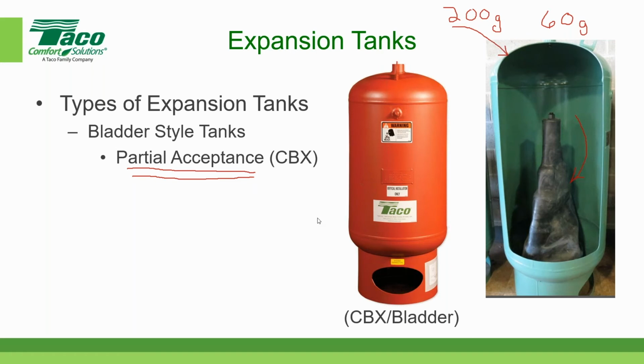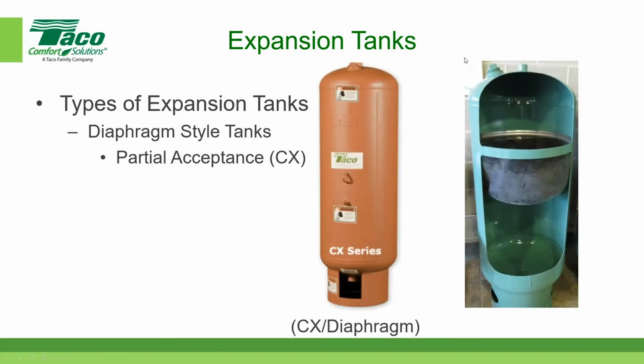Okay. And then the next category is called a diaphragm style tank. And again, that is a partial acceptance tank. In a partial acceptance tank, the steel container, again, perhaps could hold 200 gallons. But in a diaphragm style tank, since it's partial acceptance, it would also hold rather less than the 200 gallons. And the other difference is that a diaphragm style tank doesn't really have a balloon per se or a bag per se. It looks like a bowl-shaped rubber piece connected to the inside circumference of the tank.